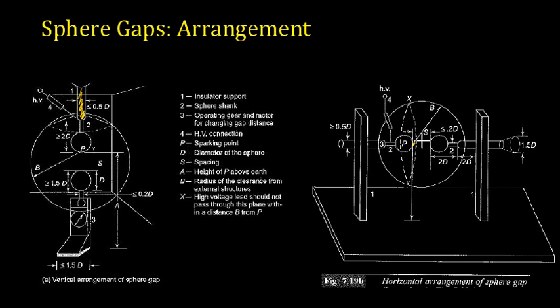So once you provide high voltage, you will have a field which is spreading uniformly in all the directions, and you can see that you will have a nearest structure which is close to the first sphere, the second sphere. So once you have uniform field around the sphere, the nearest structure is this. Once the voltage increases and exceeds the breakdown value of the air surrounding this, you will have a flashover between sphere 1 and 2.